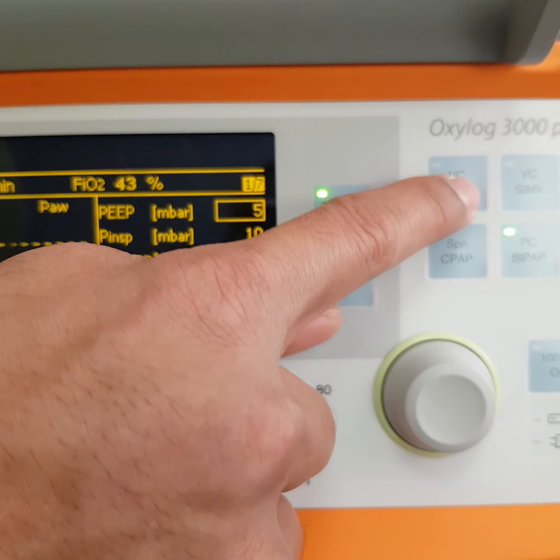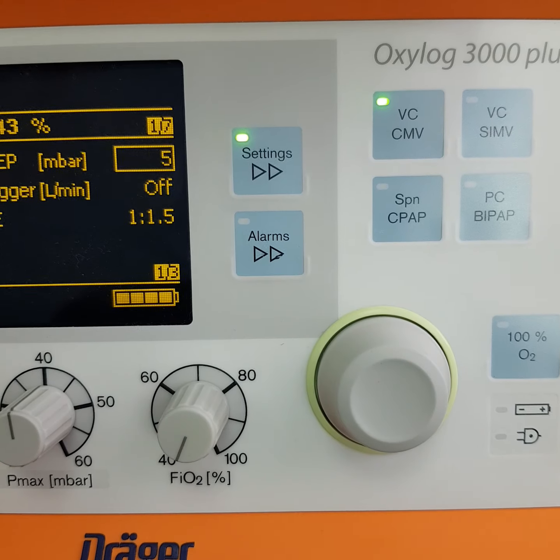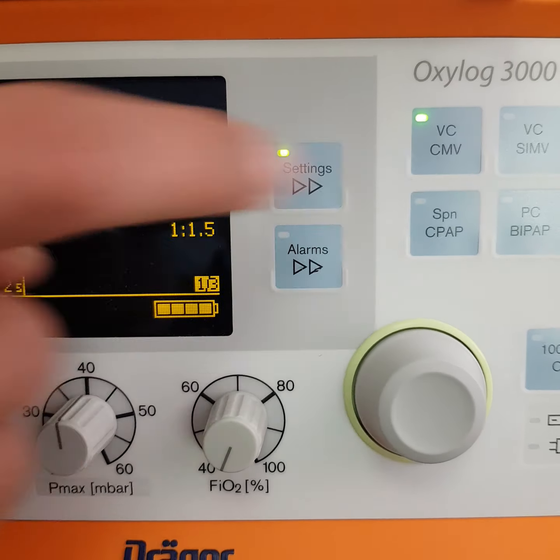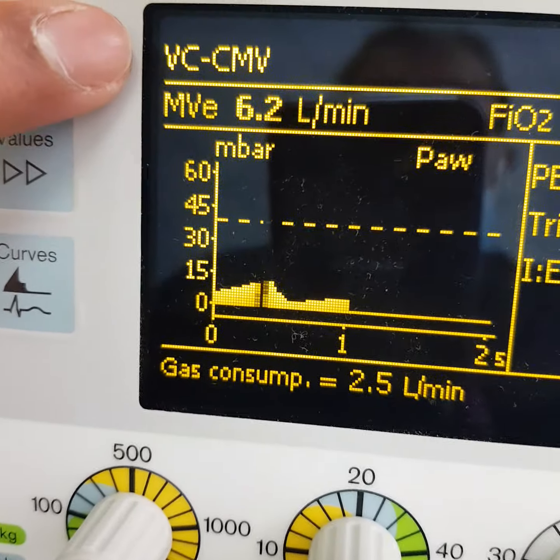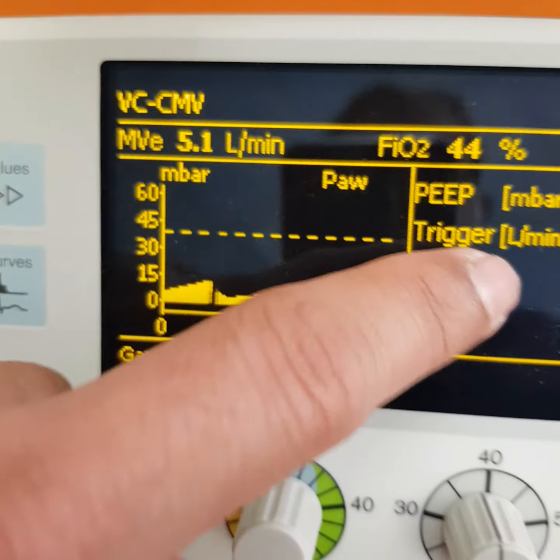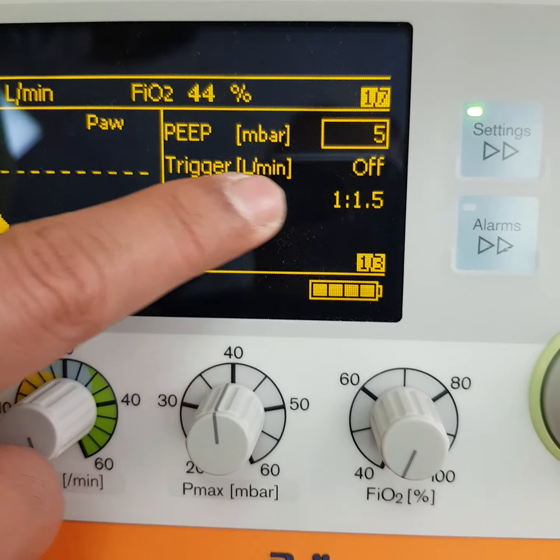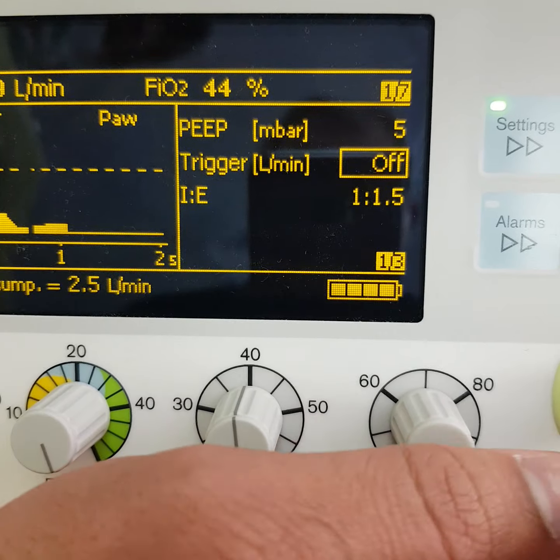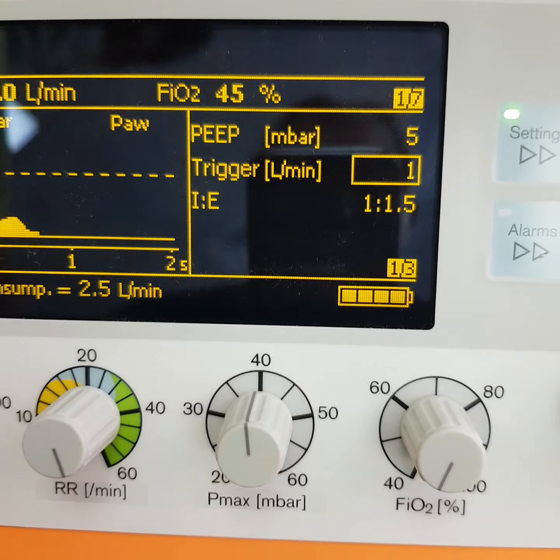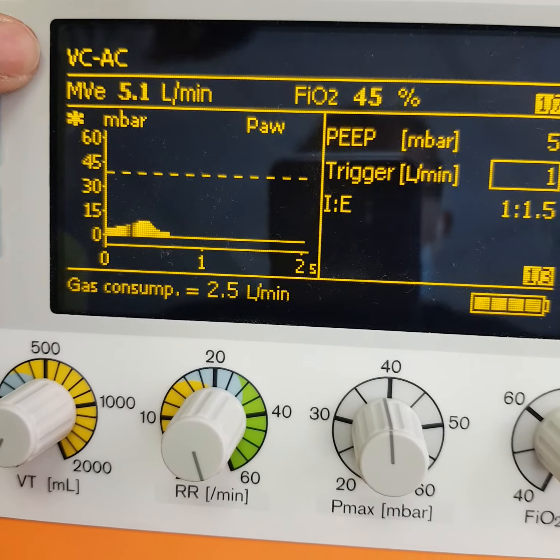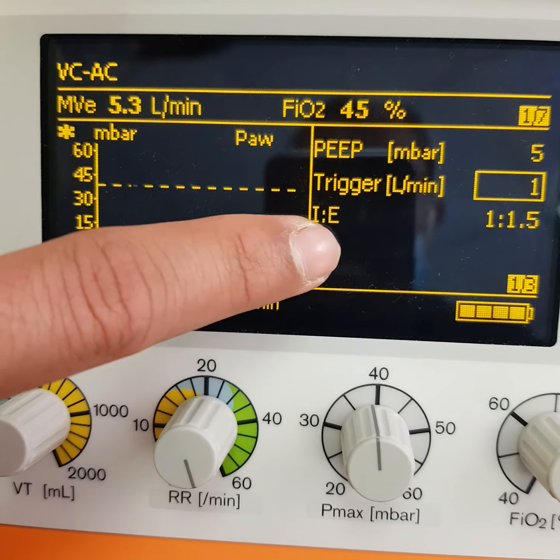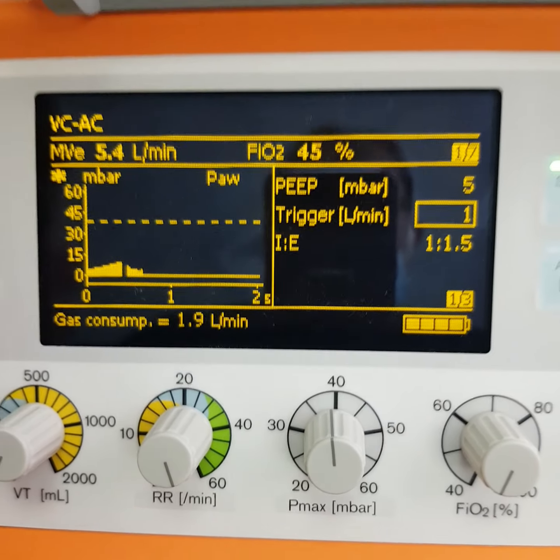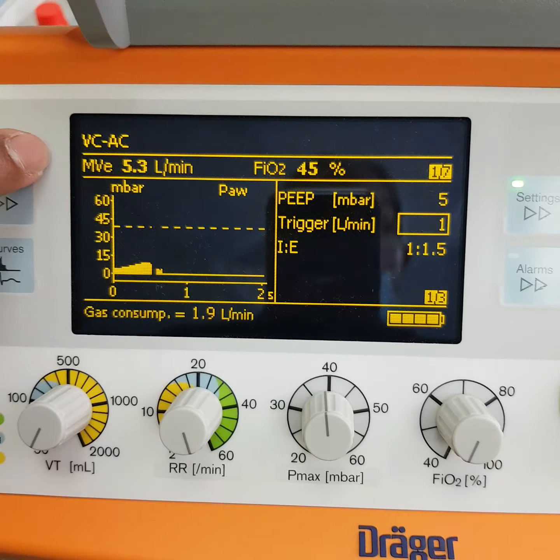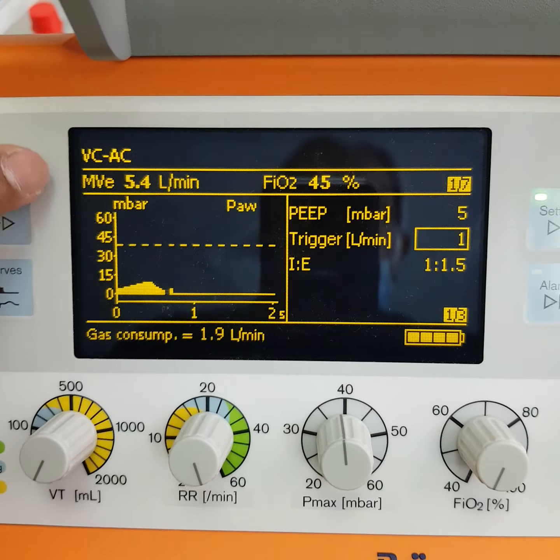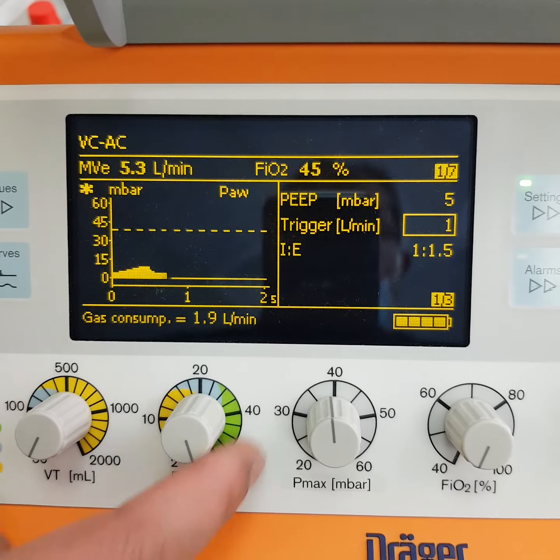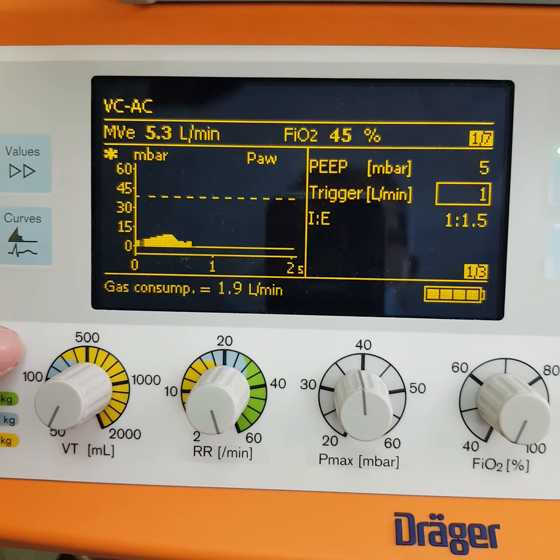Also we have one more mode. If you are activating it, the initial setup of the ventilation mode will be CMV as a default. So on volume control CMV, when you are activating trigger, right now as you see trigger is off. If you activate trigger, it will become assist control. We are on CMV, but by activating trigger it will become assist control, which means spontaneous activity is also allowed, but the support will be delivered with the same settings as CMV before.